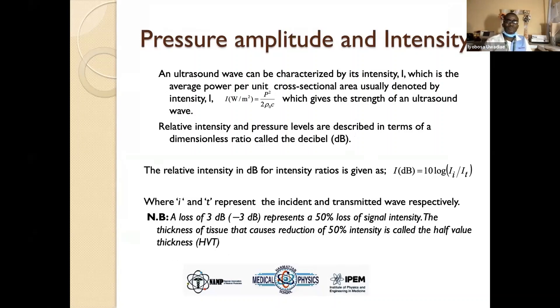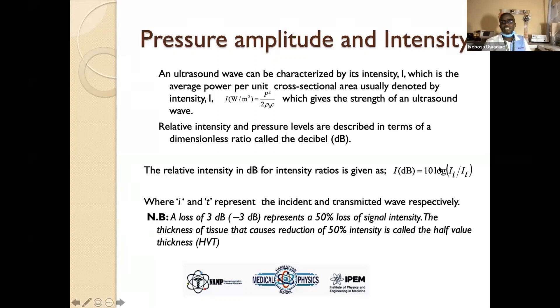From that equation, we can also look at the pressure amplitude and the intensity. An ultrasound wave is characterized by its intensity, which gives us a measure of the power of an ultrasound. Whenever we want to look at the safety effect of an ultrasound, we look at the pressure amplitude and intensity. We have this relative intensity measured in decibels — given as 10 times the log base 10 of the transmitted intensity over the incident intensity. When we get minus 3 decibels, it represents a 50% loss of intensity.